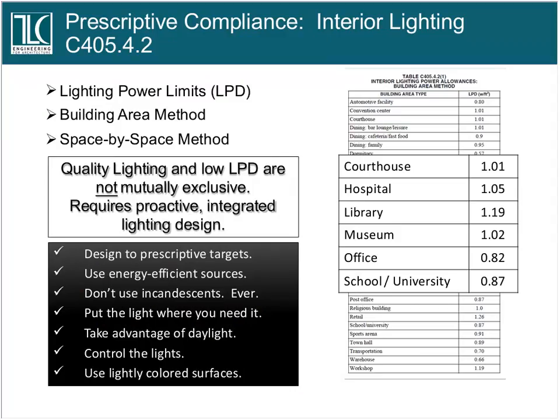So office space, for instance, no more than 82/100ths of a watt per square foot in an office building. The old code, that used to be 1 watt per square foot. So there's an 18% reduction in lighting power density in this code change from the 2009 to 2015 code. 18% reduction in lighting power density. That's huge. And once again, it's a team sport. You just can't tell your lighting designer to lower his lighting power densities because when you start lowering those lighting power densities, you've got to take into consideration what's happening in the space below.